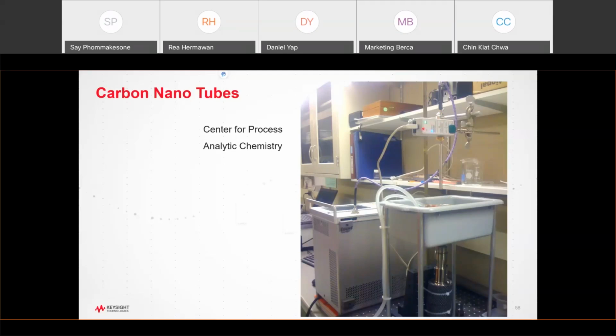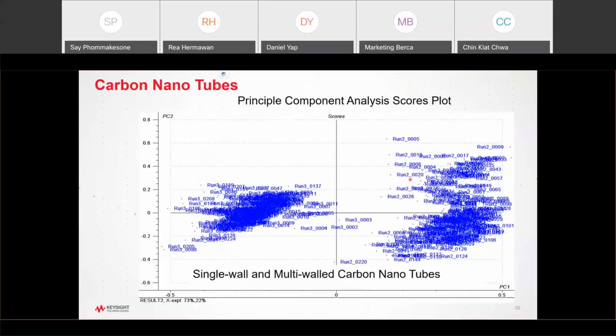And with any change in this instrument or cable change, this electronic eCal can correct for any drift in the setup. So that way you go back to the original calibration state. This will be a continual process of measurement. This is really helpful for measurement over time. And using the same software, they can clearly correlate between two different nanotube layers, 1 and 2 layers.